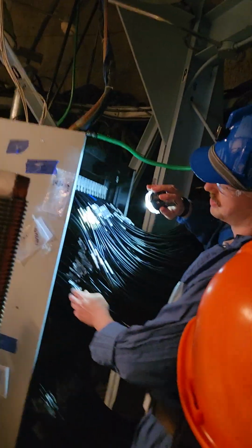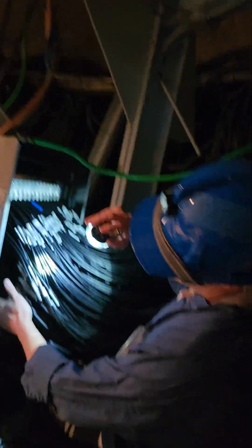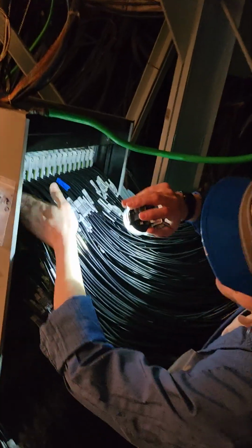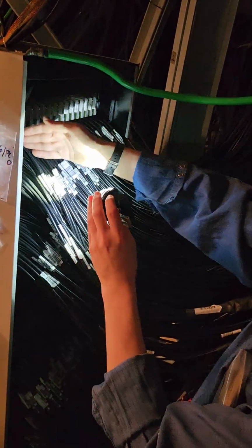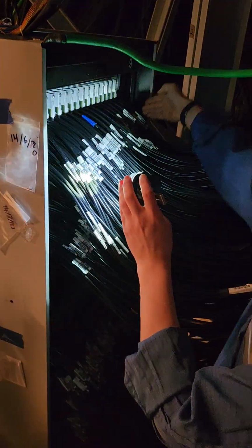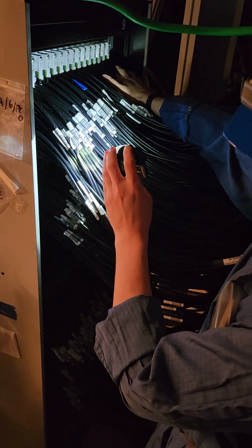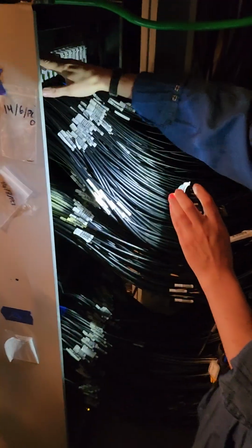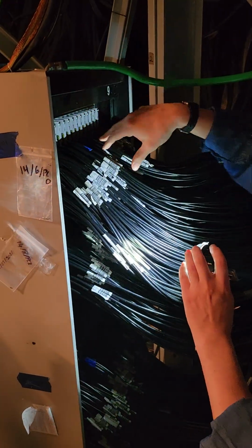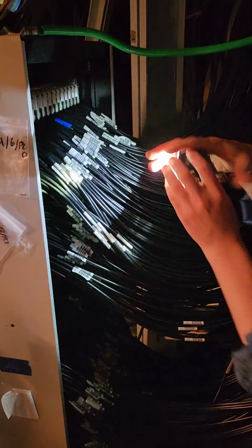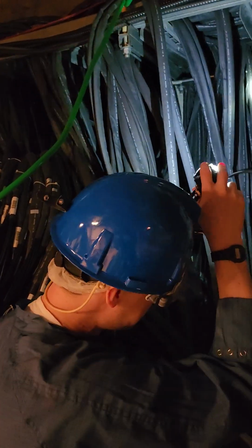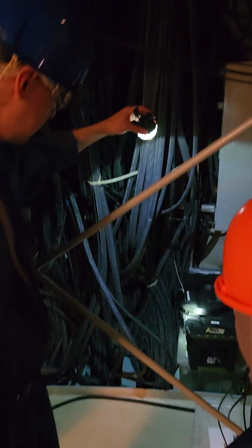This is then subdivided into 4. So you can see we have 8 cables, 8 cables, 8 cables, 8 cables, so 32 all the way here. Times 16 sections, so 512 potentially up to this. If we have 19 of these crates, you really get up to a large number. Each one of these cables is then fed out into the back here, into this whole entanglement, and eventually gone through and put through the deck there.